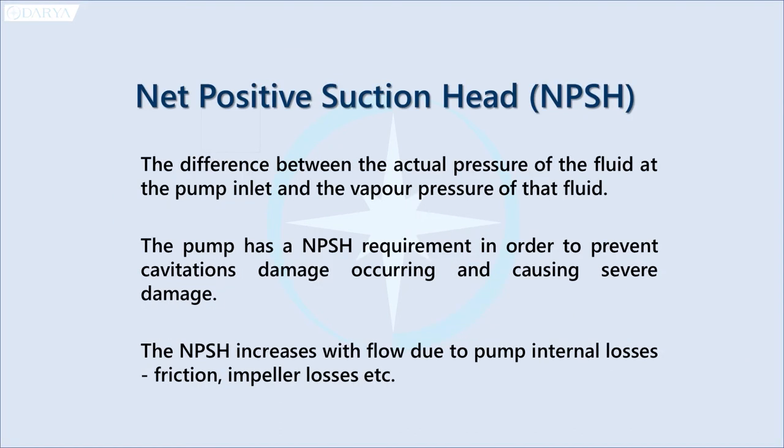Net positive suction head (NPSH) is the difference between the actual pressure of the fluid at the pump inlet and the vapor pressure of that fluid. The pump has a NPSH requirement in order to prevent cavitations damage occurring and causing severe damage.